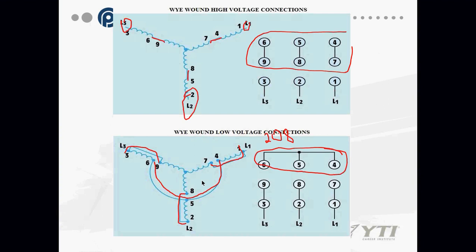Which draws more amperage? One thing that I definitely want to talk about is that the second configuration is going to draw more amperage. The first configuration is going to actually be a more efficient motor. The higher the voltages, the longer the windings. The second configuration is going to draw more amperage.